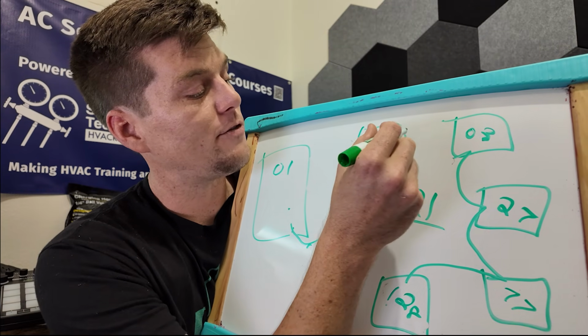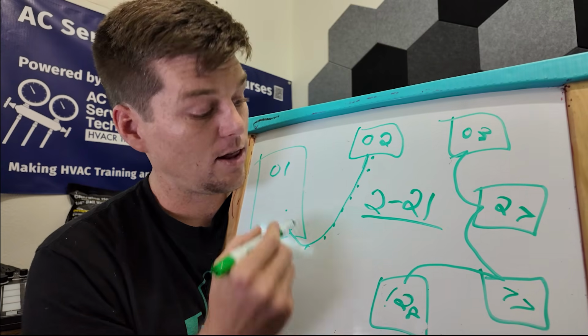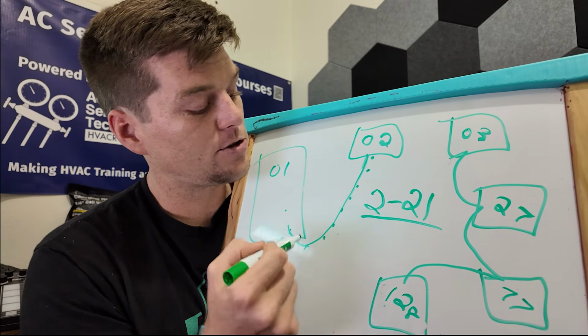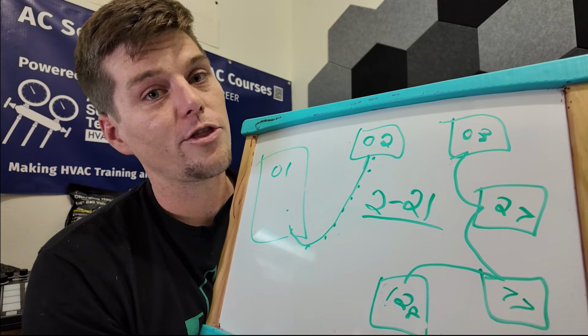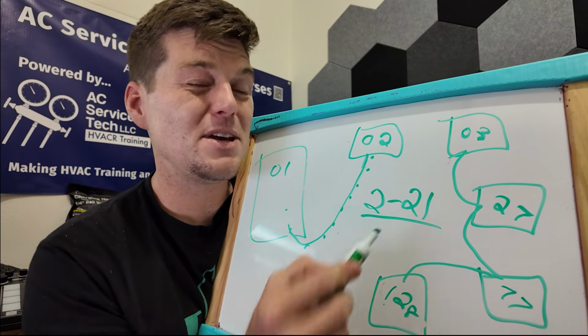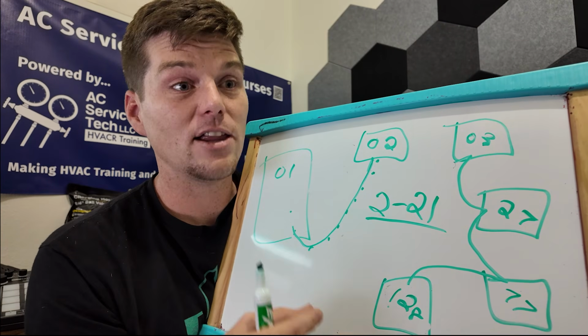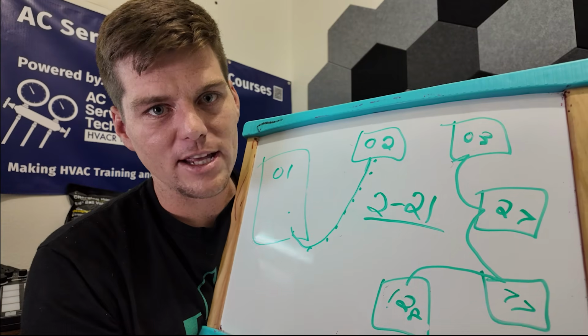So what you have to do is power cycle the indoor unit, turn it off, turn it back on again while it's in 221 to reestablish communication. Now, if this indoor unit starts to see the data packets coming down the stream to the first indoor unit, it will lock the thermostat out within 5 minutes. If you want to speed that process up, you can actually turn the thermostat on after the power cycle to tell it to actively run. It's going to start looking for orders on the network to see what it needs to do.